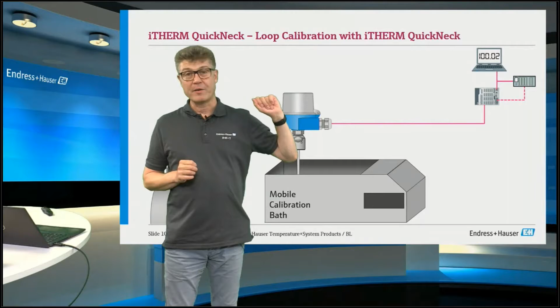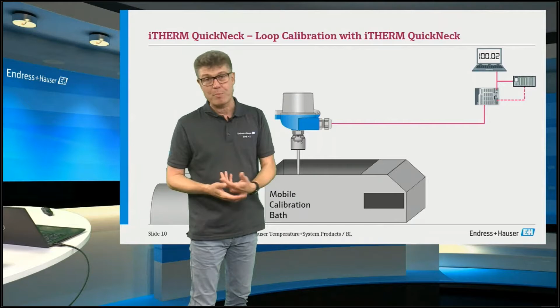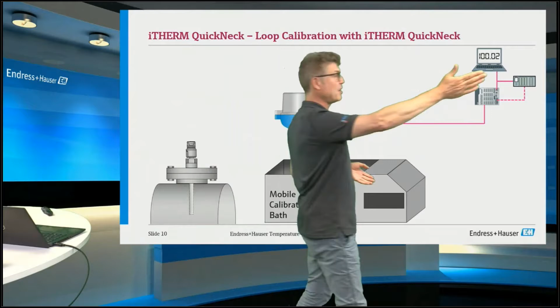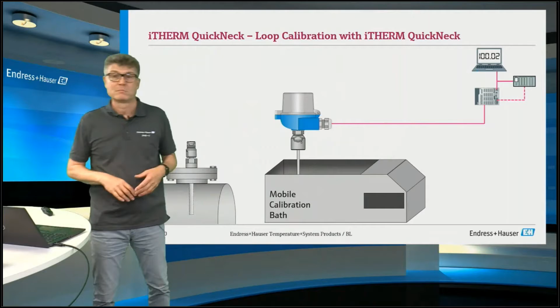The input card of your DCS, the output of the transmitter, and so on - so you need to do a simulation or whatever. If it stays connected, you can skip this because the DCS is still online and you always see what is happening. That means you do this calibration by accident: you connect your sensor to the DCS, to the 100 degrees calibration bath, and then you immediately see on your DCS screen 100.02, which is probably inside the tolerance.